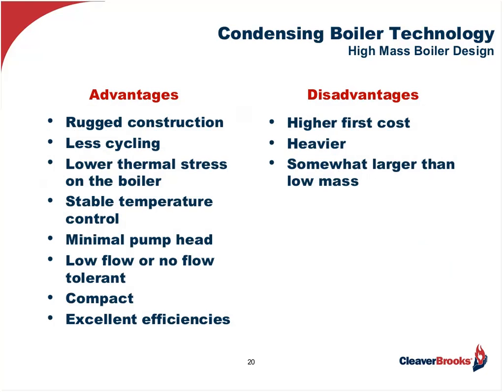Now, comparing them to high mass boilers, those are typically constructed more ruggedly. Because they have that mass of water, they're not going to cycle as much. That water acts as a flywheel. That leads to lower stress on the boiler, and very stable temperature control, because they're not heating up real quickly. And high mass boilers typically have less than 10 feet of head, and more typically only about 5 feet of head. So they have minimal effect on your pump.